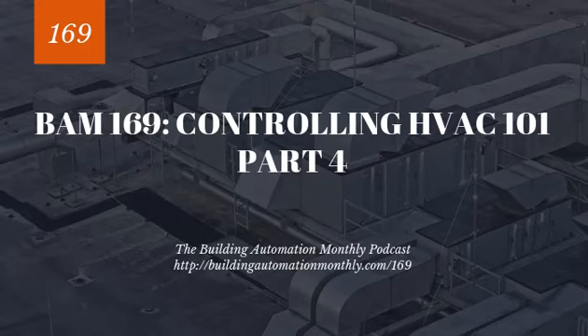Now, what if you have multiple hot water boilers? Well, in this scenario, you kind of have three strategies, and those are Unison Control, Staged Control, and Lead-Lag Control. So Unison Control is one of my favorite controls, as long as the boilers are all sized the same. You control them by basically running them all at the same time, and you fire the same fire rate or same temperature set point across multiple boilers.